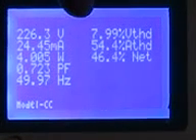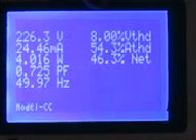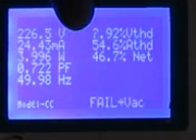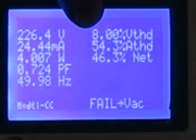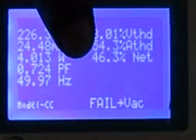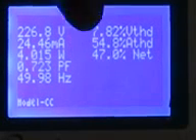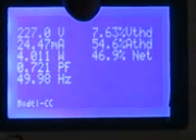For an idea, as you can see, there is a presence of voltage THD. Due to this, the ampere THD also contains this factor, so the net THD caused by the load is 46, which is the difference of current THD and the voltage THD.